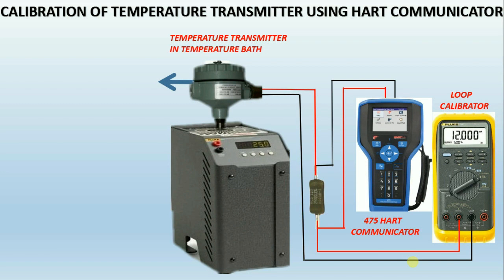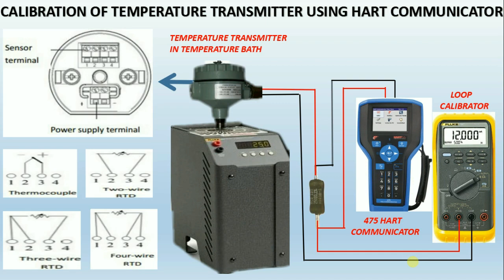Many calibrators can be used both as dry or liquid baths. The temperature element with transmitter is inserted in the temperature bath for calibration. Now we will see how to calibrate a temperature transmitter using HART. Connect the loop power to the temperature transmitter as shown in the elevated view, then connect the temperature element to the transmitter sensor connection terminals, according to the configuration done in HART.